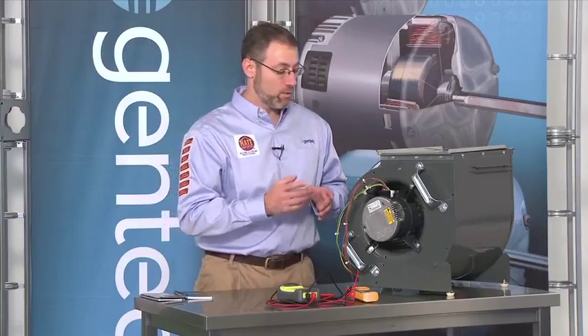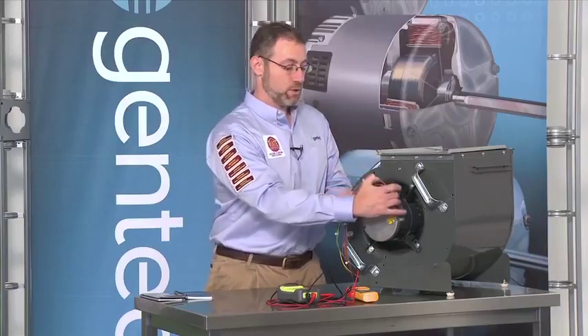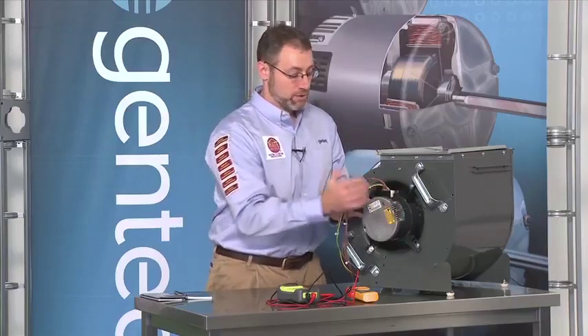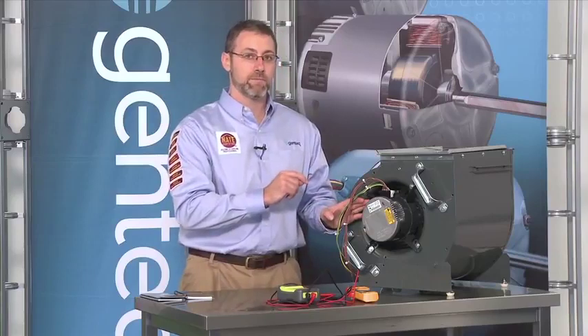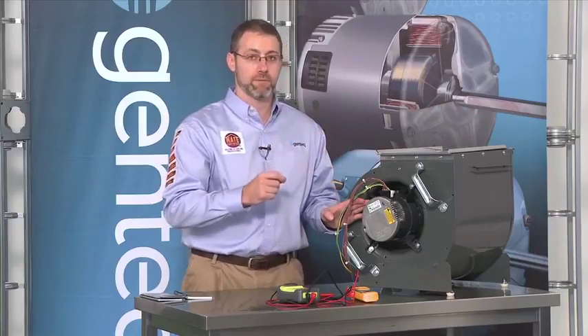There's really only a couple of things to remember about X13 when replacing it. One of them has to do with where the motor is in its mount. The motor has a control in this part of the shell. So what you'll see is there's little dimples on the motor, and we want the motor bracket to be mounted towards the shaft from those little dimples. You can see that in this picture here. So basically the only special criteria for mounting the motor is that the motor be mounted towards the shaft from the little dimples that are in the motor shell, so that we don't clamp the belly band mount over where the control area is in the motor.